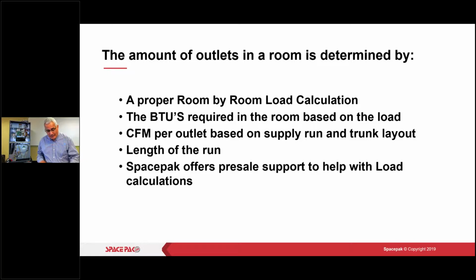So yeah, I've got my total load for the job, but I need to know my load on a room by room basis so I have the proper amount of outlets per room. This is where you can get in trouble if you're not doing it right. Again, run the most plenum you can, get as close as you can, so our 2-inch drops to the rooms are not going to be too long. And if we go longer than 15 feet, remember your 10% rule.